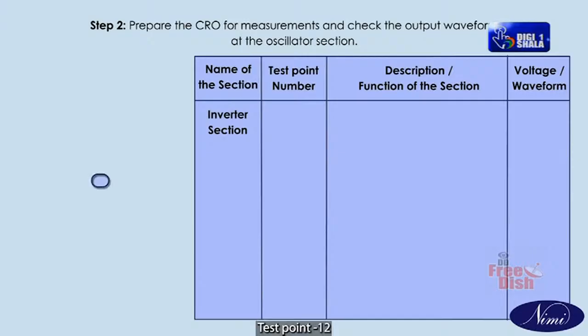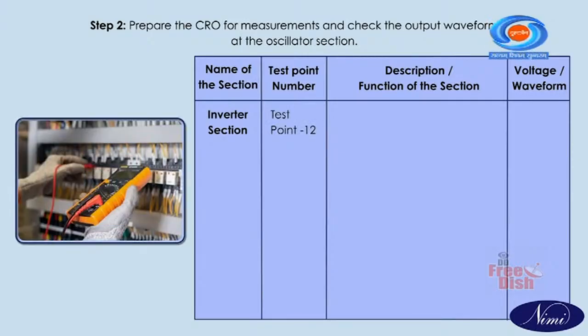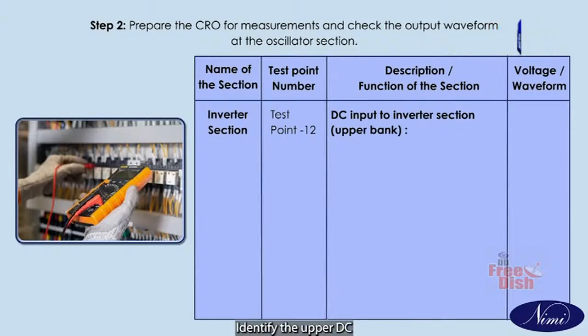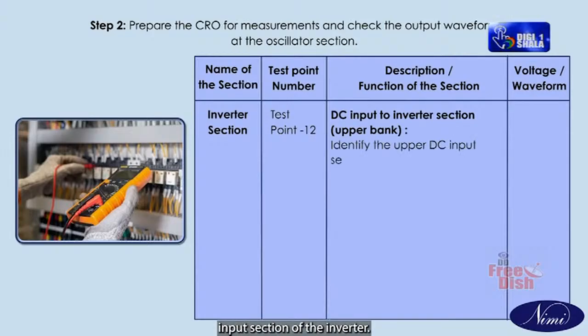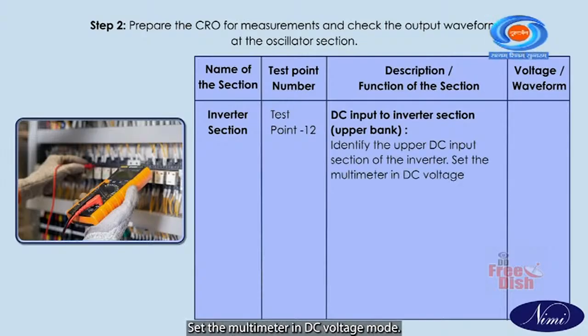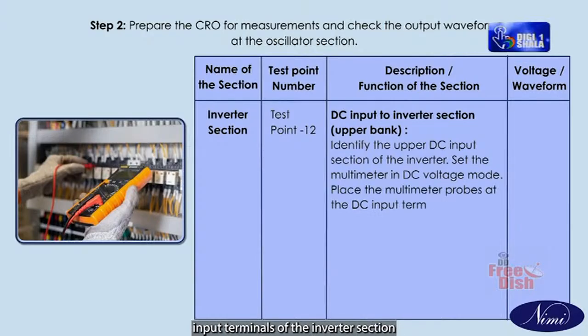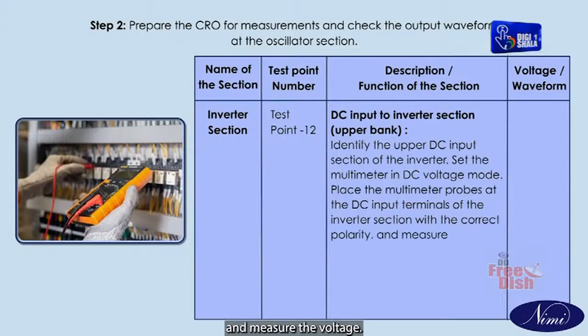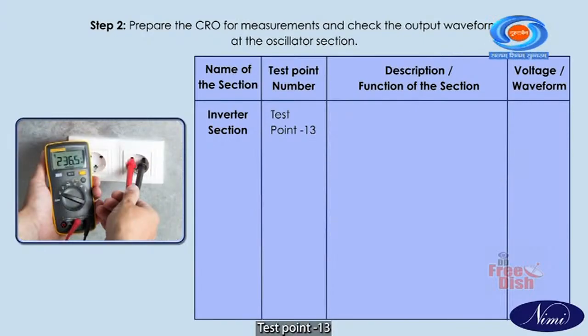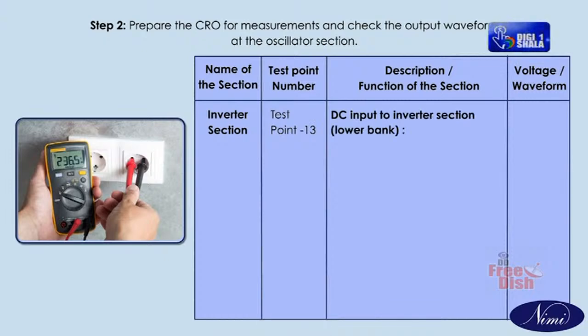Inverter section. Test point 12. DC input to inverter section, upper bank. Identify the upper DC input section of the inverter. Set the multimeter in DC voltage mode. Place the multimeter probes at the DC input terminals of the inverter section with the correct polarity and measure the voltage.